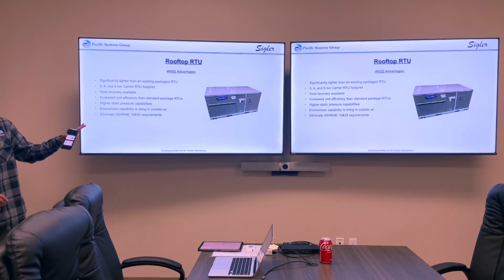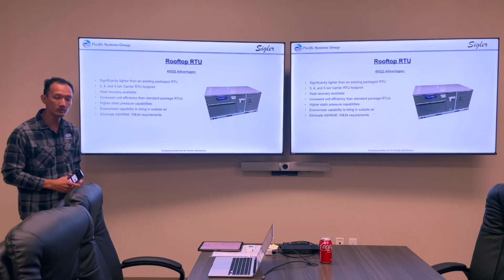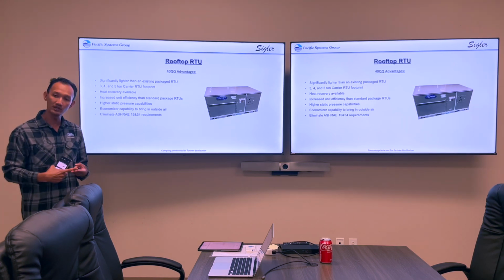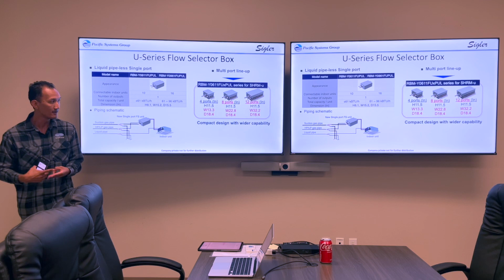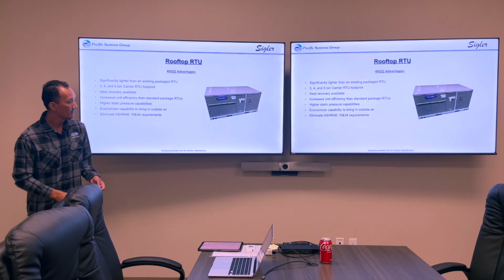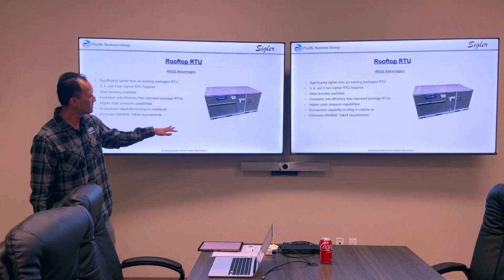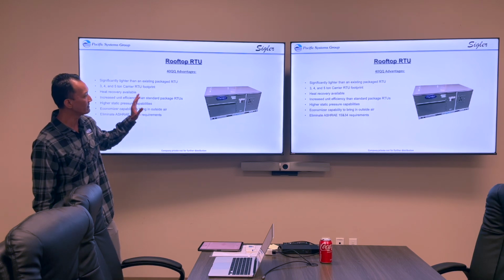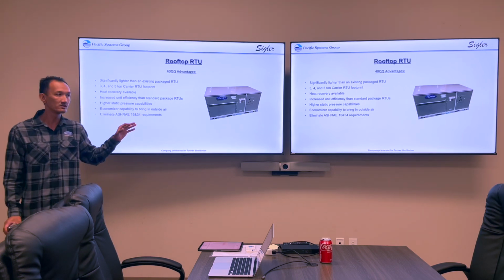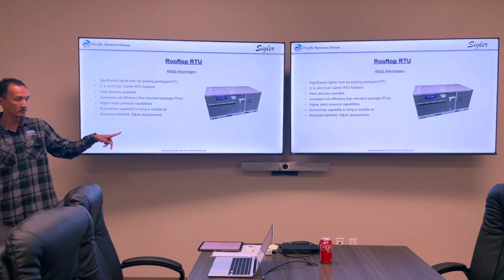It looks like a standard carrier rooftop, and that's because it is. It started its life as a standard carrier rooftop, but we took out the condenser coil, we took out the compressor, we took out the condenser fan. And we left the evap coil and the evaporator fan in there, and what that allows us to do is connect these to a VRF outdoor unit.